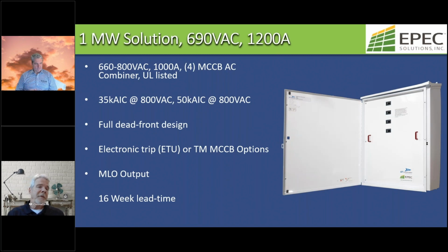Just a little deeper dive on specific products. For the 1 megawatt solution that Frank was showing earlier, we have a 4-breaker AC combiner as shown over on the right. That unit is designed and UL listed for 660 to 800 volt, up to 1,000 amps, and has up to 4 molded case circuit breakers installed. Those breakers, as you see down below, can either be electronic trip or thermal mag. Electronic trips are limited to 35K AIC at 800 volt. The thermal mags can go up to 50K AIC at 800 volt as well. So again, as you see, it's a full dead front design, main lug only output, and this rack mount equipment we can ship in a 16-week lead time. Next slide.